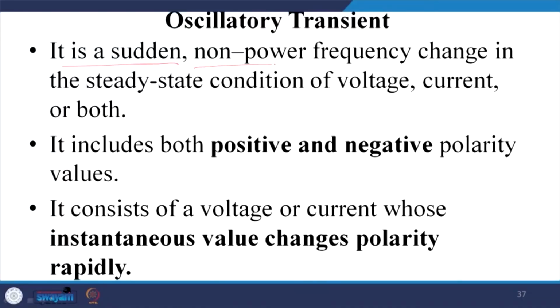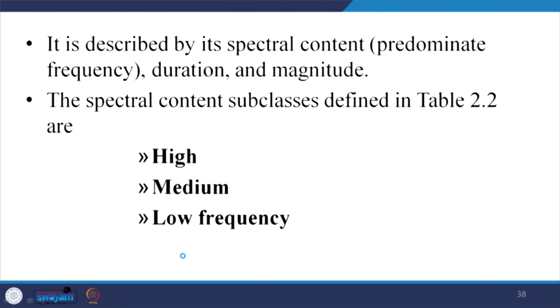Now, the oscillatory transient. It is a sudden, non-power-frequency change in the steady state condition of voltage and current or both. It includes both positive and negative polarity values. It consists of a voltage and current whose instantaneous value changes polarity rapidly. It is described by its spectral content, determined by the frequency, duration and magnitude. The spectral content subclasses are defined as high, medium and low frequency. These are the classifications of this transient.